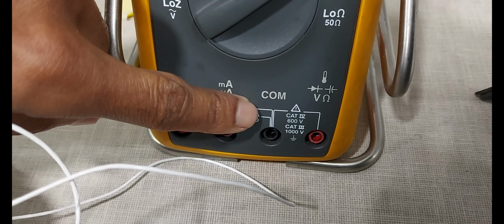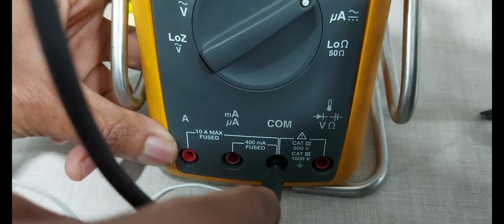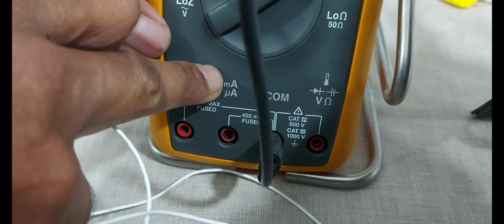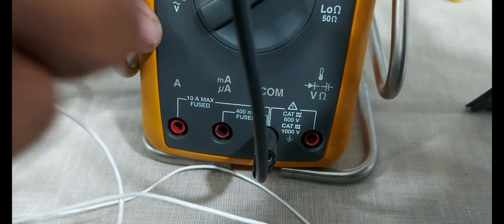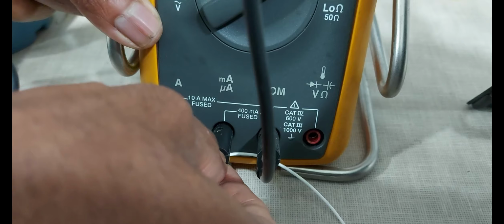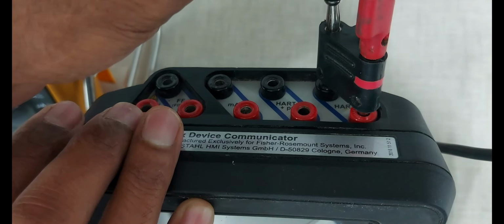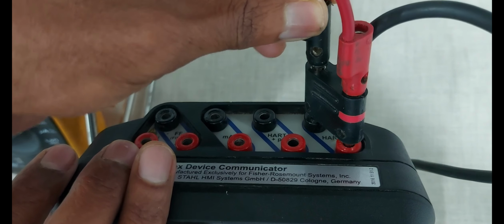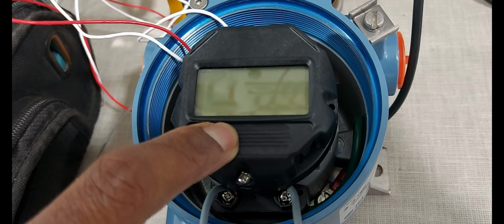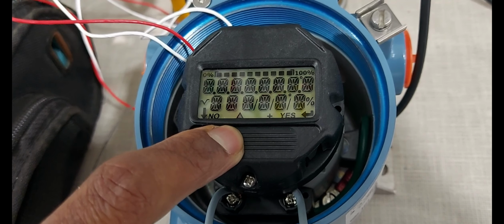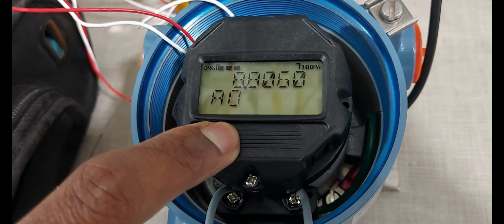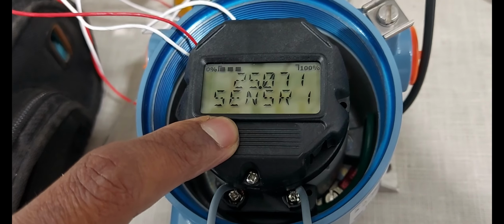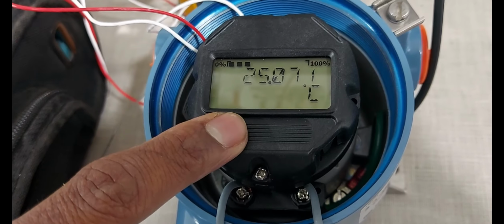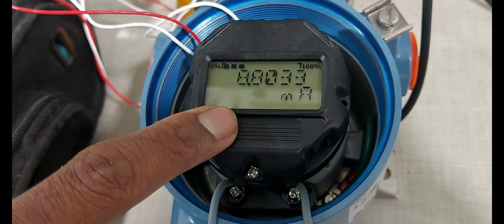We are connecting the reference multimeter common port. Connect. Next we are connecting the multimeter milliamp measuring port. We are connecting the black test lead to the negative transmitter terminal line. Now the transmitter is powered on. Wait. Model number, analog output. We have already set 25 degrees. Analog output is also showing fine.